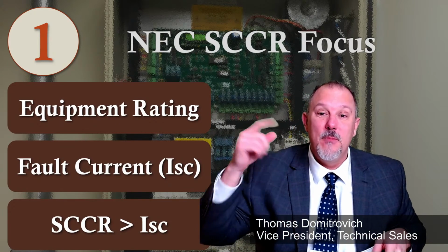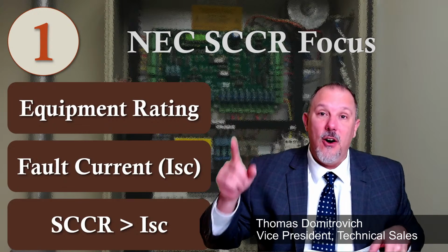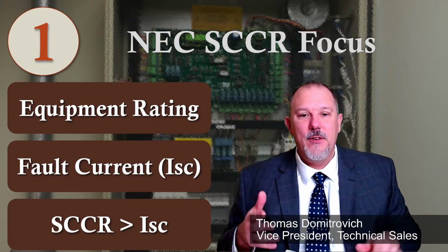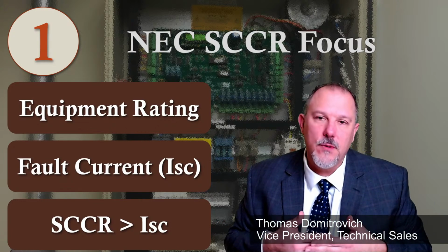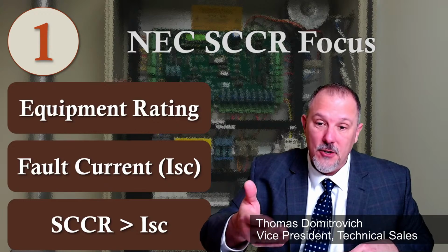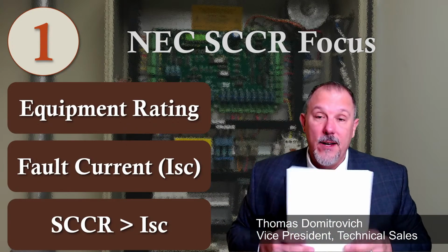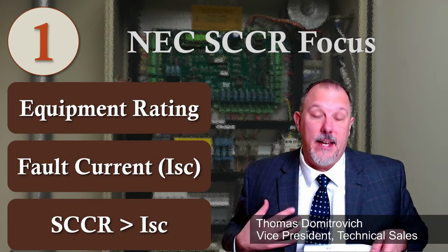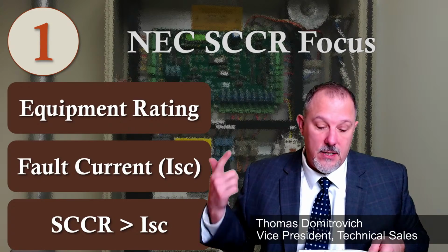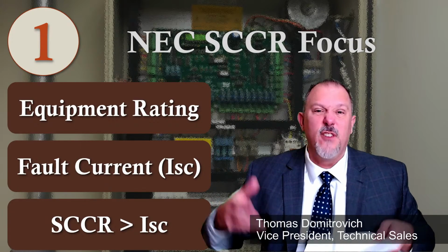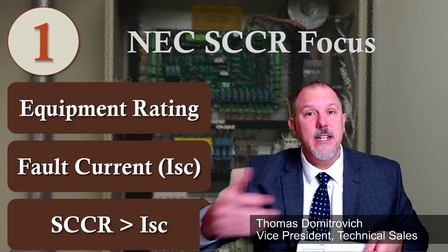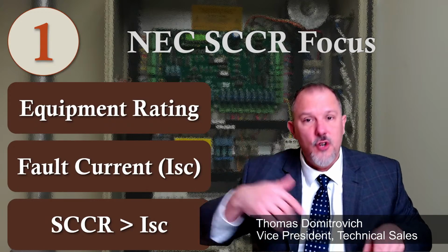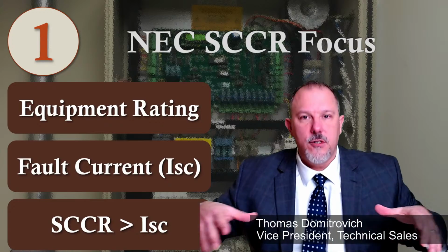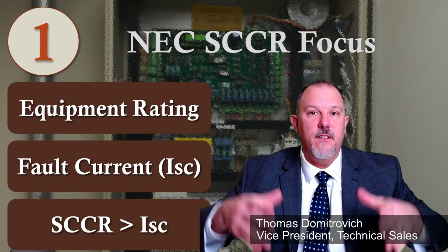It requires you to mark the SCCR on that equipment, and then, doing that evaluation, who's going to do that? The electrical inspector, the consulting engineer who's aware of the changes. He's going to be going, well, these are the calls I get. Pittsburgh, Seattle, Washington, downtown New York. They have a lot of fault current, and these are what we call secondary distributions, grid networks, where you have networked transformers in downtown areas. The available fault current at the bottom of those buildings is well over 100,000 amps.